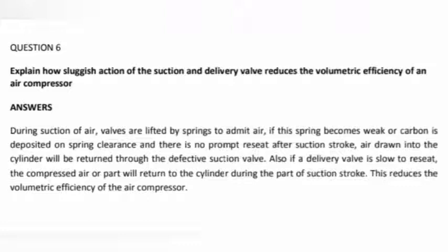Also, if a delivery valve is slow to reseat, the compressed air or part of the compressed air will return to the cylinder during the part of suction stroke. This reduces the volumetric efficiency of the air compressor.